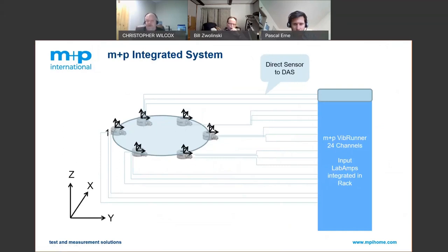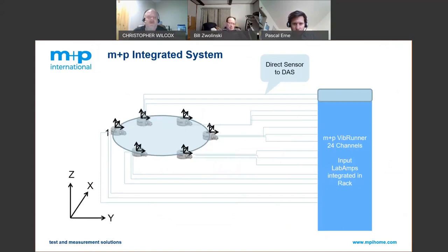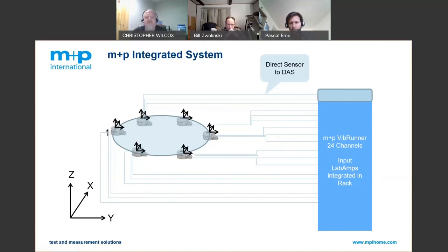What M+P International has done is incorporate all the math and summing into the controller. This greatly reduces the number of actual fault paths. The force sensor is taken directly into the M+P system or through the lab amps for charge conditioning. This allows monitoring of each and every sensor for overloads or open channels. Because it is all digital, there is no need to repatch between runs when switching from X to Y or Z axes — you simply repatch the control output. An additional benefit is that all sensitivities, ranges, serial numbers, and part numbers are stored within the result file, which is excellent for traceability and documentation.